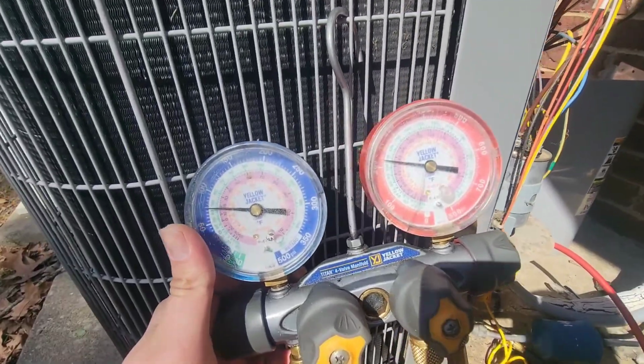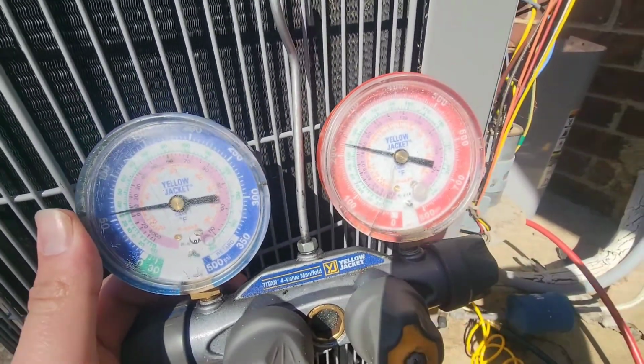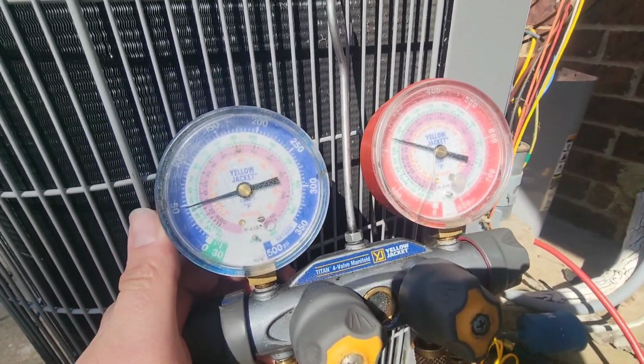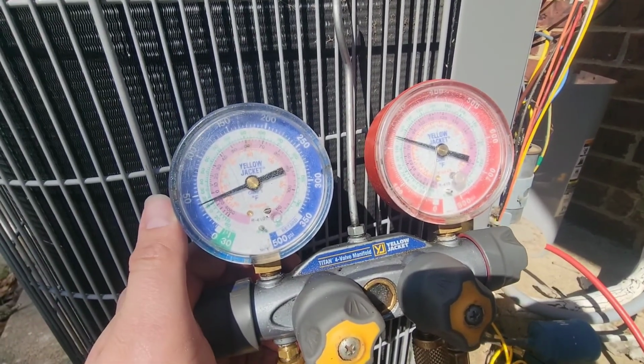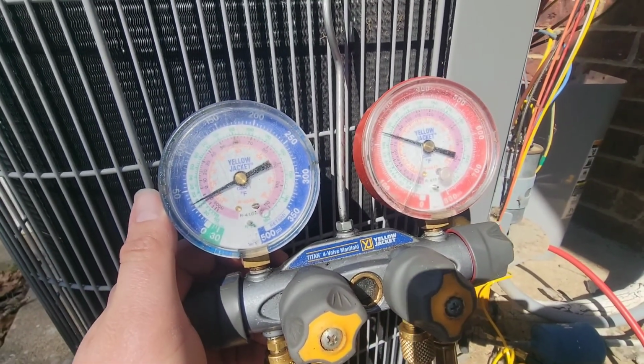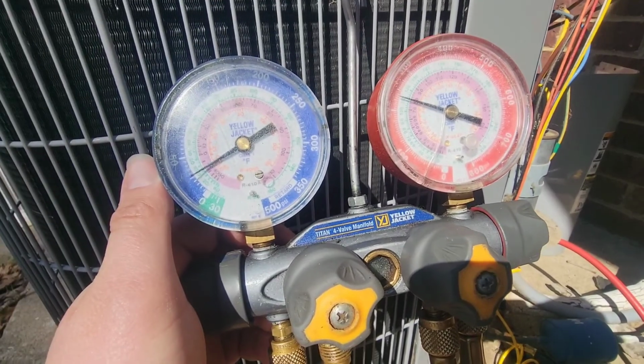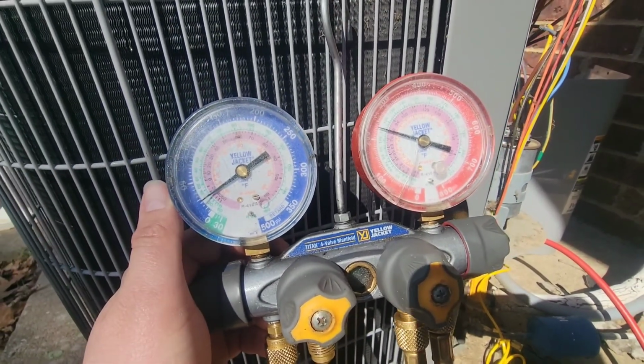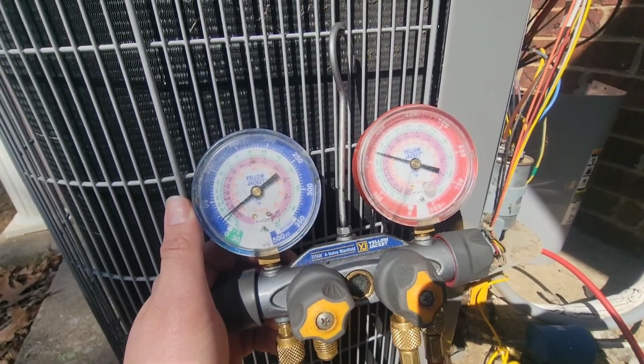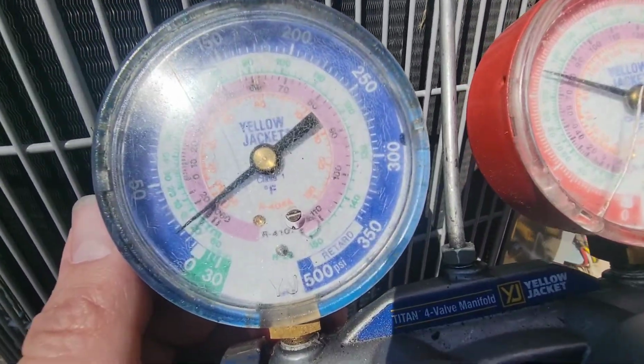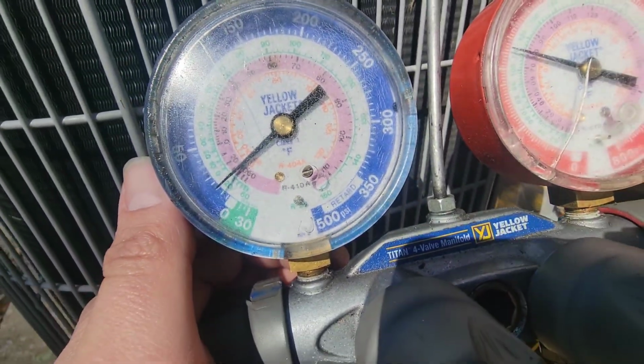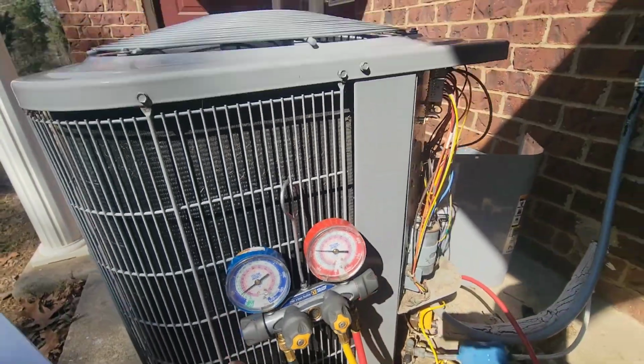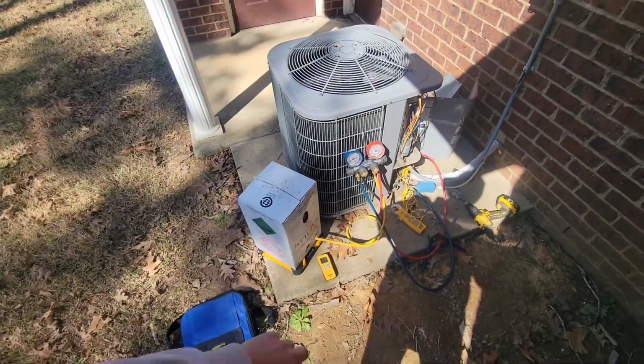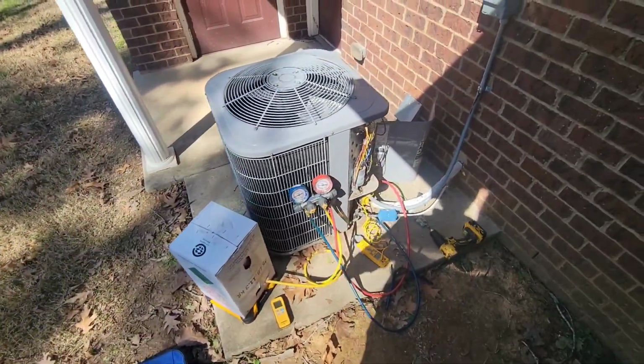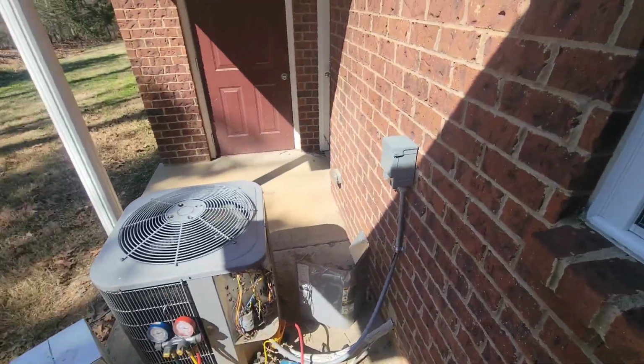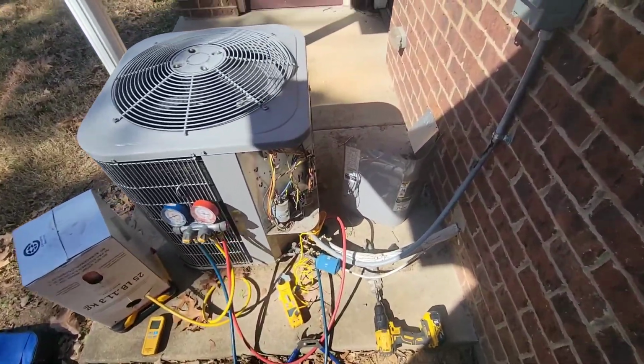Got the gauges hooked up. Low side, high side's about 225. Low side is going down. Okay. So we're in the heating mode. It's about to cut off. You can hear it pulling down. You hear that sound? 15 PSI, it's about to cut off. There it goes. So low pressure switch is cutting the unit off. It'll kick back on here in a second. It'll try to operate, and of course it's gonna kick back off.